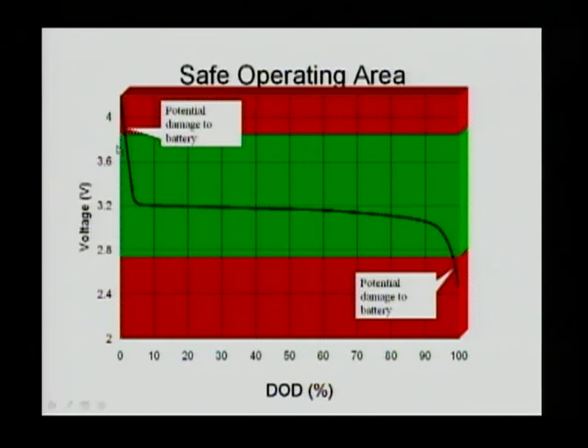On the other hand, if you charge the battery voltage too high, you can also have premature damage to the battery electrodes. Therefore, you want to maintain the battery at roughly no more than 3.8 volts on iron phosphate batteries. On other chemistries, the voltage range may be different, but overall there is a range when you charge and discharge the battery — you don't want to overcharge, and you don't want to over-discharge.